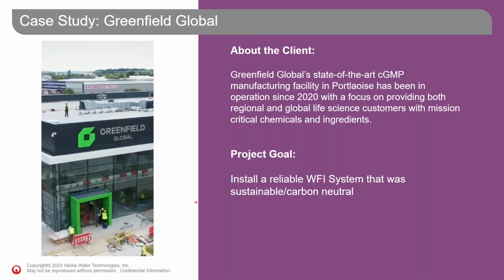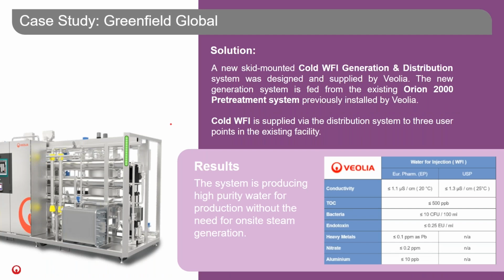Just some case studies. Greenfield Global was a company looking for a state-of-the-art GMP manufacturing facility in Portlaoise, and this has been operating since 2020 to manufacture their WFI system products. They were looking to install a reliable WFI system that was sustainable and carbon neutral. They had some green goals that had to be met as well. So the solution was a cold WFI production unit and a storage and distribution system. We provided them with an Orion 2000, a 2 meter cubed an hour unit, with some pre-treatment as well, to the distribution system. And it was producing water to quantity and quality on site for WFI standards.